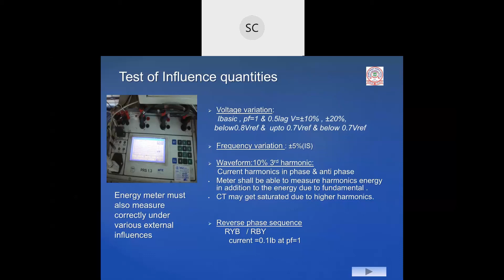Then next comes reverse phase sequence. In case of reverse phase sequence also, the meter should record correctly. Test of ambient temperature influence: these are the conditions, plus or minus 15% ambient. Normally we consider 27 degrees as the ambient. So a coefficient value is defined, and the formula is defined for the error.